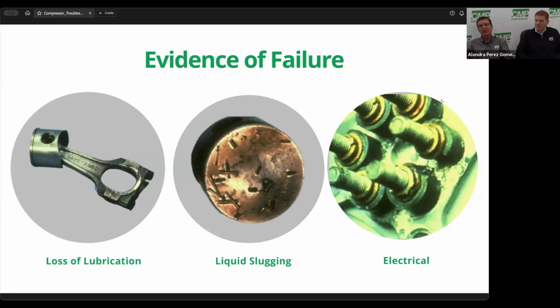While I'm talking about valve plates, something I always hit in my seminars: if you buy a Copeland compressor valve plate kit, whether it comes from CMP or wherever, you're going to get several valve plate gaskets, and they're all going to look the same to the layman. But the one you want is the one that matches the cylinder wall exactly, 100%. The difference in those gaskets is the bore size. If you put one on that's hanging over inside the cylinder, it's going to knock when you turn the compressor on.